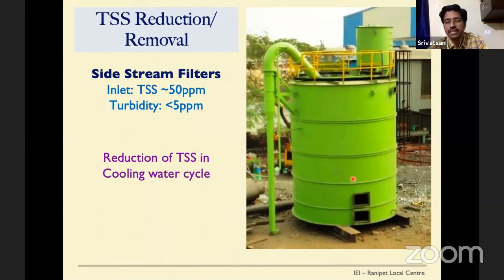This is a side stream filtration system which we use in the cooling water cycle. A portion of water is treated in this system for removal of TSS. Here the TSS level is around 50 ppm, and the treated water's TSS level is less than 5 ppm.